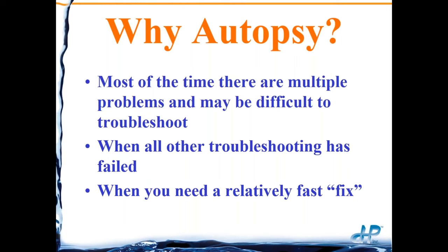Keep in mind, a membrane element autopsy is a destructive test. We are going to cut apart this element and dissect it to find out what actually happened to it, so you won't be getting this element back.